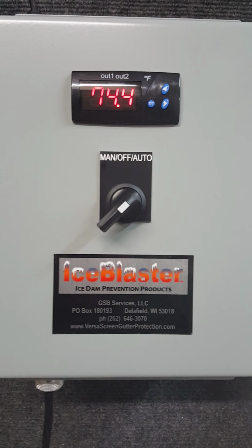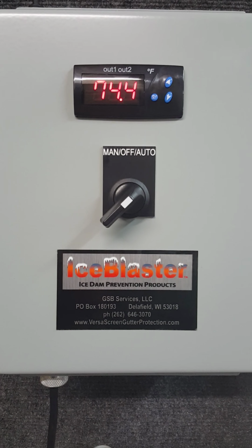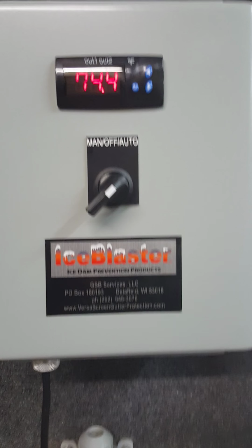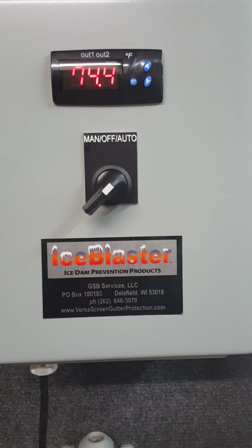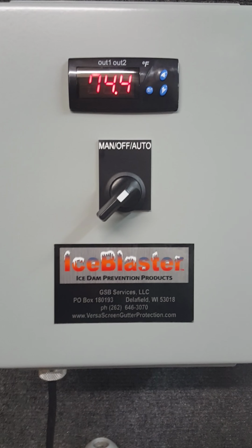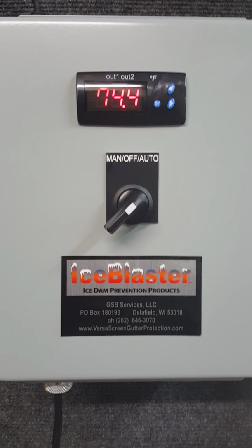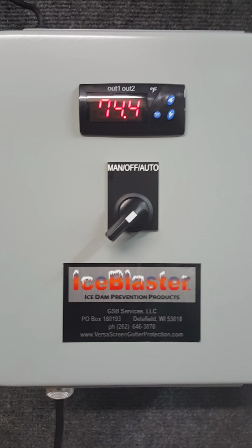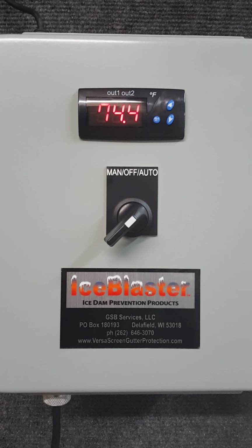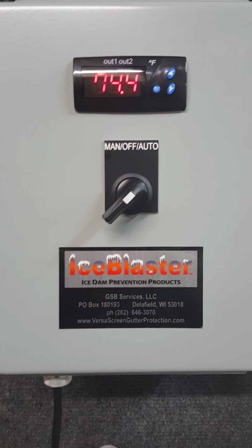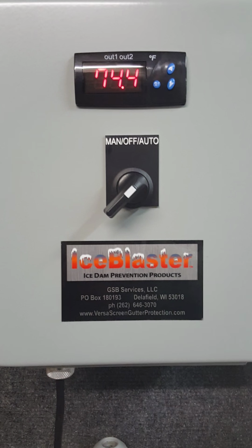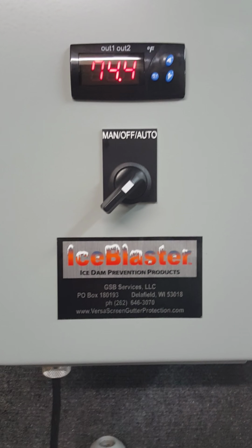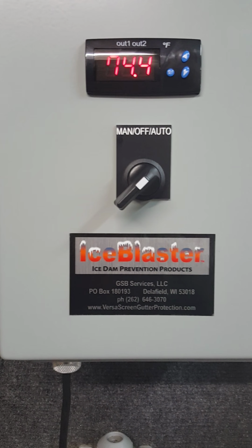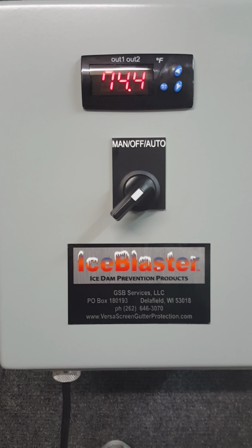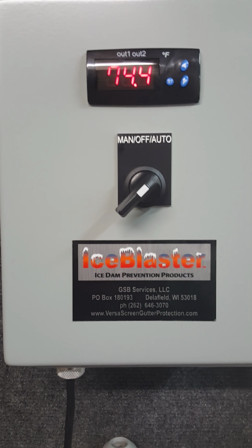That snow runs down to the bottoms of valleys, gutters, roof edges, all those areas, and it encounters much colder air because now it's exposed. It can refreeze there. And that's how ice dams start, with those repeated cycles. So this controller is designed to have the heat cables on in that window. So if it's above 35, 36 degrees or below 5 degrees, the heat cables don't need to be on. Now, perhaps in your situation at your home, those parameters aren't exactly right. We have the opportunity to adjust those settings.